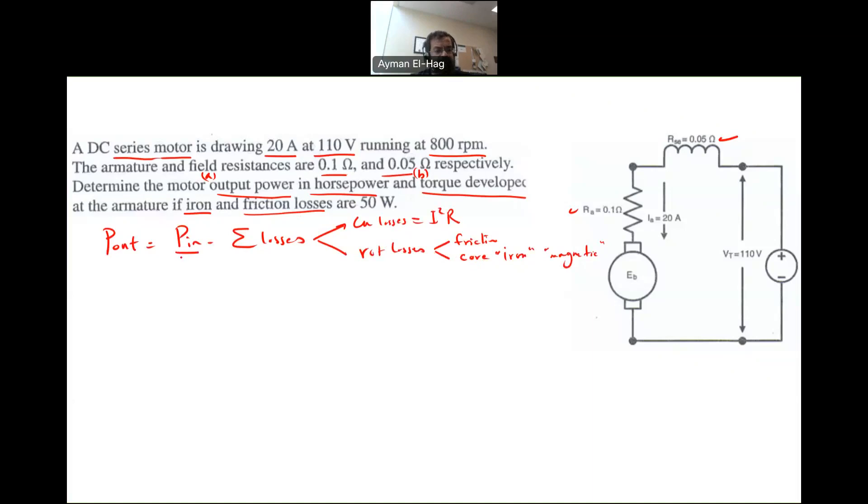So first you need to find P in. What is the input power for this motor? Very straightforward. It is V terminal times IA, which is 110 volt times 20 amps, and this will give us 2,200 watt. This is your input power.